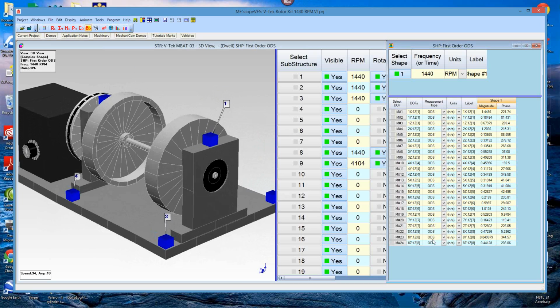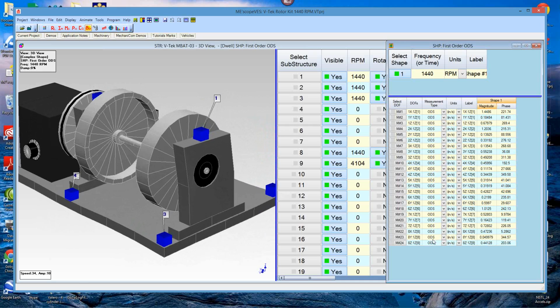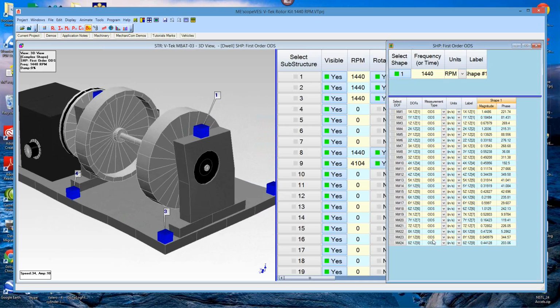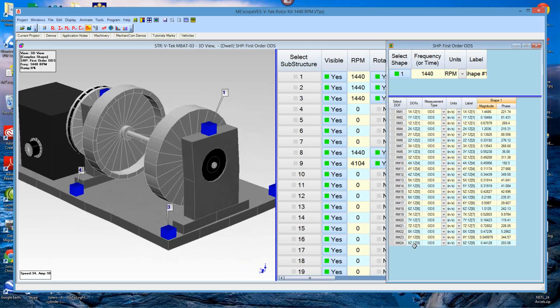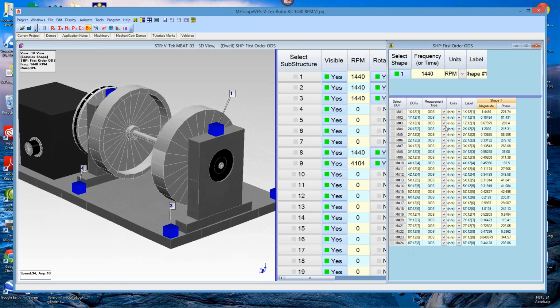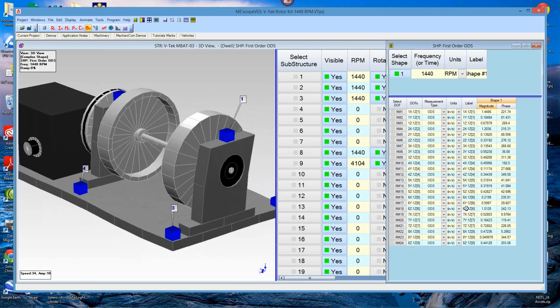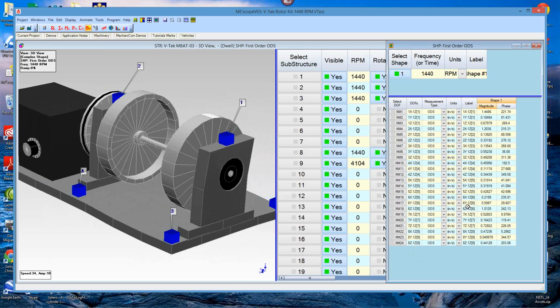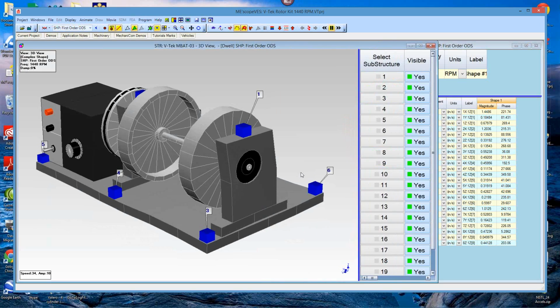Very easy to do in ME'scope. Used SDM to attach the bearing blocks to the base plate, and then use those mode shapes in a curve fitting scheme, a least squared error curve fit, to fit the ODS data, and we can do that in real time. So as the ODS changes for the 24 accelerometers, we can change the animated picture for literally thousands of degrees of freedom.